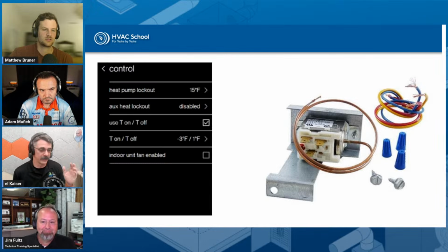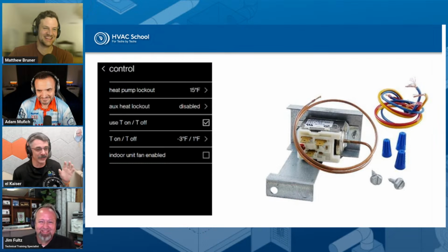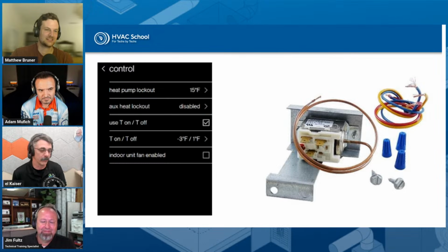And of course, this was back in the days of, if you were lucky, you had a chronotherm. Yeah, I call that unlucky. But in the day, it was the whiz bang thermostat. But most thermostats back then were just a 2-bulb mercury thermostat. So you had to have like a 2-degree droop to hit that second stage. As soon as it hit that second stage, that's how they cycled in and out of it, with the second bulb on that mercury thermostat. And they would just bang on every bit of electric heat they had. And it was uncomfortable as all get out.